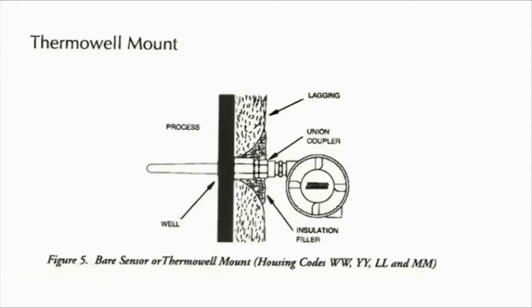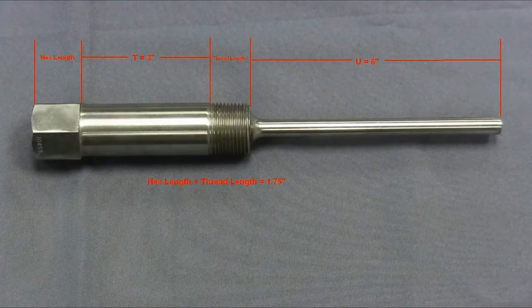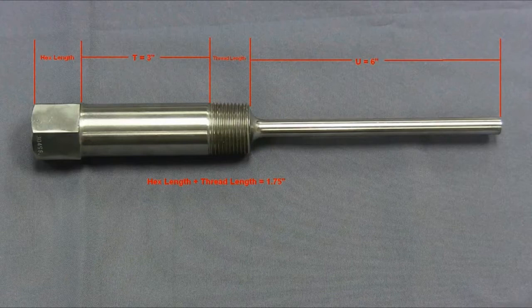The T lagging length is an extension added to the standard 1.75 inch thread and hex length. It is primarily used to extend the well connection through insulation, making it accessible to install or remove. Taking these dimensions, we find the thermowell has a U length of 6 inches and a lagging T length of 3 inches.